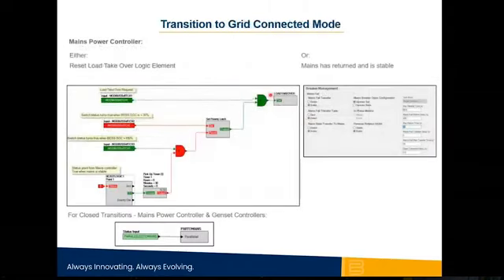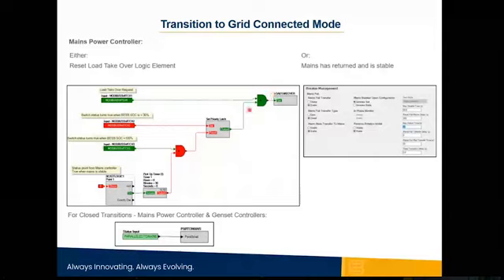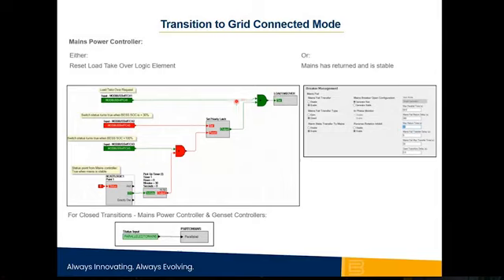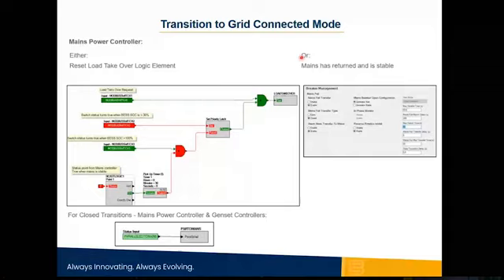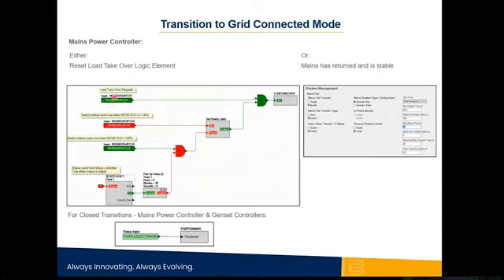If we're transitioning to grid connected mode, then we can do that in two ways. If we're coming out of a planned transition, we need to take away load takeover logic. Or if it's coming from an unplanned transition, then our settings here will take care of that. In the case where it's coming out of a planned transition, like demand response, where it's time to transition back to utility power, we had the load takeover request, but then we set a latch when the state of charge was less than 30%. The state of charge is now at 100%, so we're trying to reset this latch right here. And the latch will finish resetting when the mains is stable after 30 minutes based on this timer. So when this timer times out, the output will be true.